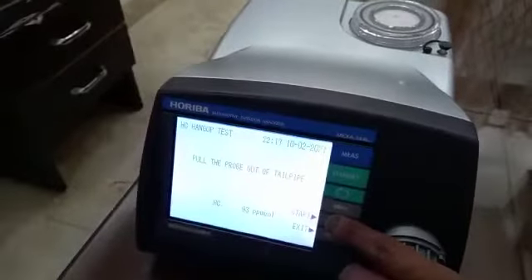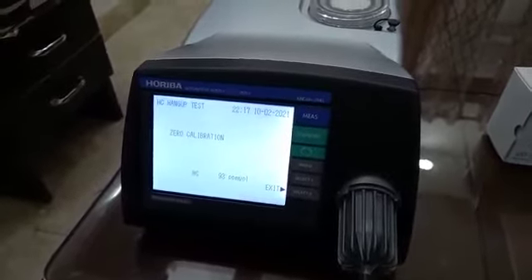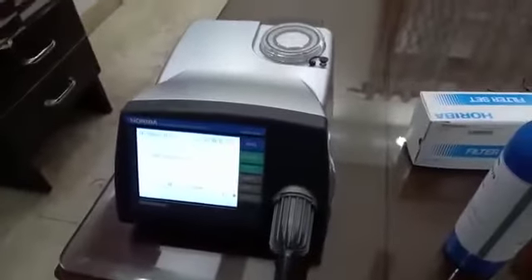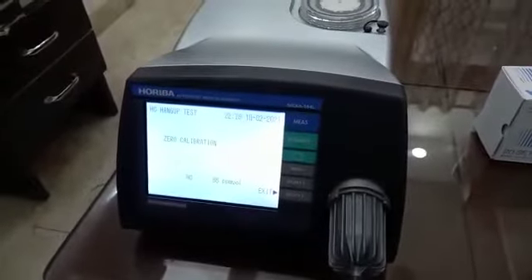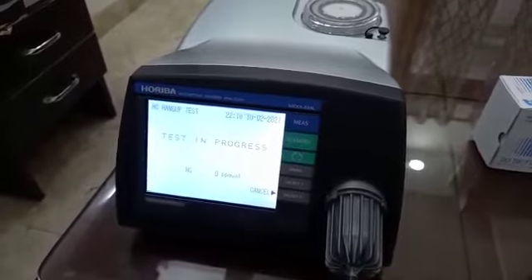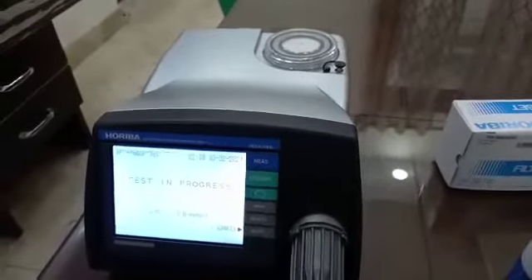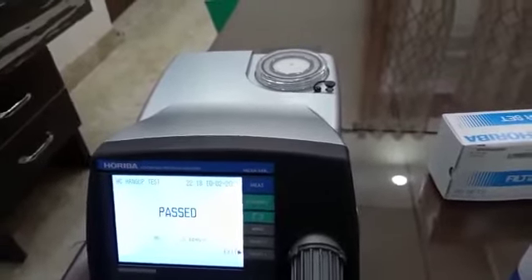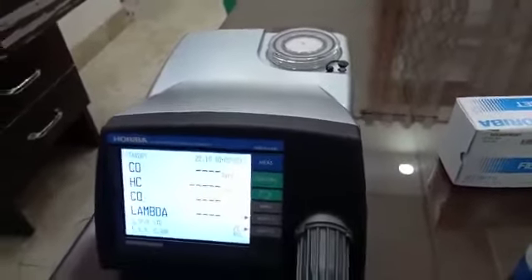After the leak check, we have this HC hang up test, and prior to the measurement, the machine verifies itself for the content of HC in the emission, and it takes the emission accordingly. There's a zero calibration which is done by the air at the back. Inside the machine, we have an air filter. We need to open this whole assembly for the same, from where the air passes and ensures the zero calibration. So whenever we are doing the HC hang up test, it's getting passed now. The purpose is basically to ensure that the HC content in the whole sampling line is below 20. Otherwise it will lead to higher readings of the HC and may fail your tests.